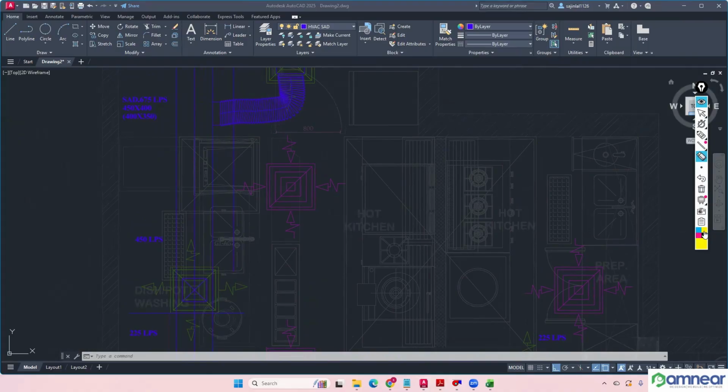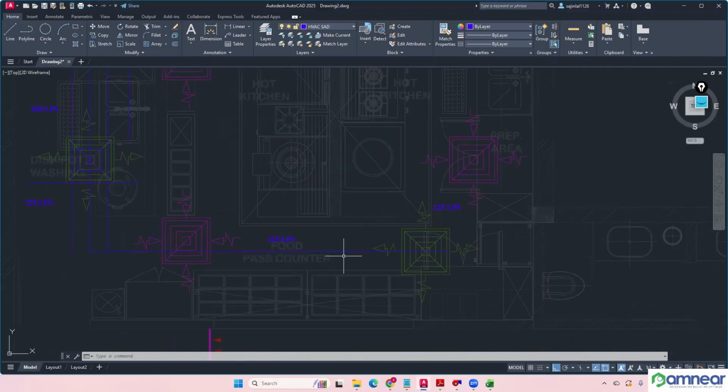So since the diffuser neck size is 300, and the duct is having a width of 400, from the bottom of the duct a 300 mm collar, 300 mm rigid duct drop we can easily make. Means if you want to take the rigid duct drop, the width of the duct should be at least 50 mm higher than the diffuser neck size, then only we can take it, right? And we have studied that. So you have to make sure, because the neck size of this one is 300 only. So this duct should have at least a width of 350, then only we can accommodate it. Otherwise, we have to go for flexible duct and plenum box.